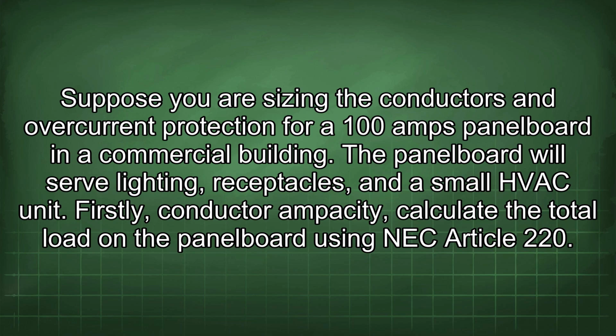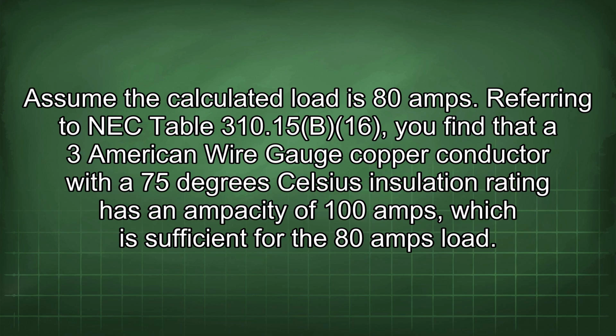Suppose you are sizing the conductors and overcurrent protection for a 100 amp panel board in a commercial building. The panel board will serve lighting, receptacles, and a small HVAC unit. Firstly, conductor ampacity. Calculate the total load on the panel board using NEC Article 220. Assume the calculated load is 80 amps. Referring to NEC Table 310.15(B)(16), you find that a 3 AWG copper conductor with a 75 degrees Celsius insulation rating has an ampacity of 100 amps, which is sufficient for the 80 amp load.